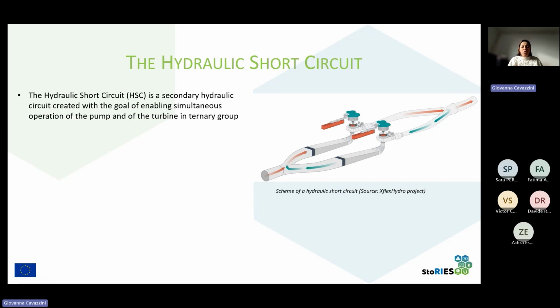But now, with this secondary hydraulic circuit created, it is possible to operate the two machines simultaneously. Of course, this will require the so-called quaternary group, so adding an electric machine in order to have the possibility of operating both machines simultaneously. The advantage of this solution is that it increases the operating range in both modes, since the net power of the power plant is equal to the difference between the power absorbed by the pump and the simultaneous power generated by the turbine.